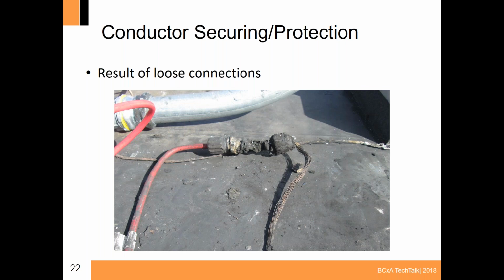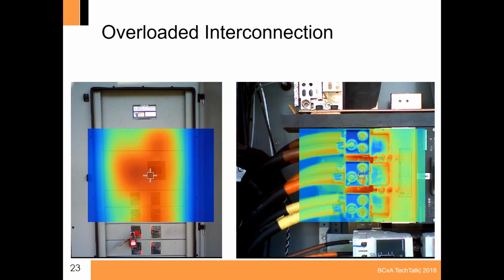And then this is an unfortunate result of a loose connection that was not found prior to starting up the system. So in some very rare cases, we see some of these unfortunate events. Again, thermal imaging. In this example, the main PV breaker, which was right in this location here, this is a PV panel board, or what we call an AC combiner, basically bringing a bunch of inverters together through these circuit breakers on a very large system. But it was undersized for the expected load. So normal operation was very close to its limit, its current rating, but it caused excessive heat. So it wasn't enough current to trip out the circuit breaker, but enough to cause excessive heat.